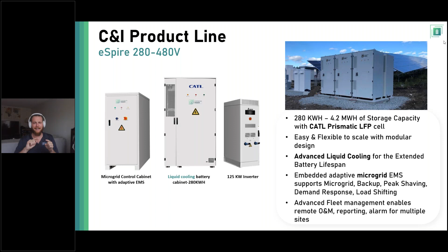Just to show you a super rudimentary line diagram for this system, we do have a more technical example that I can distribute after this call, but this is in general how we're AC coupling the system. And that's a good thing to note. This system is going to be only AC coupled for now. I think there's some development down the line for potentially DC coupling these with a DC to DC charge controller, but for now, the eSpire 280 is going to be AC coupled only. So you can see the power conditioning system AC coupled to say a 600, 800 amp panel. The size doesn't necessarily matter. It really matters just so we can size contactors for islanding if we need be.